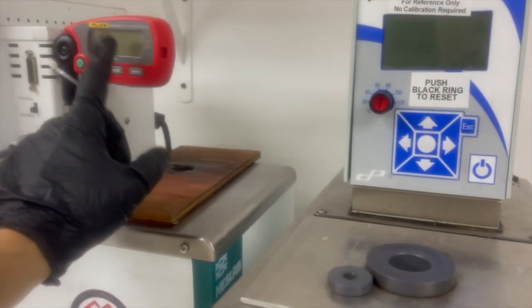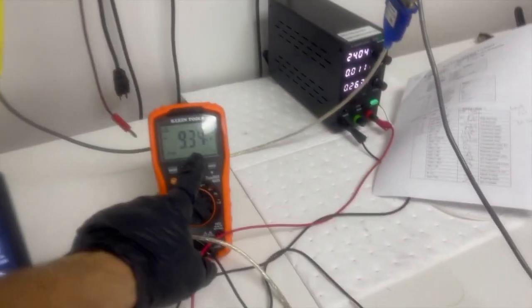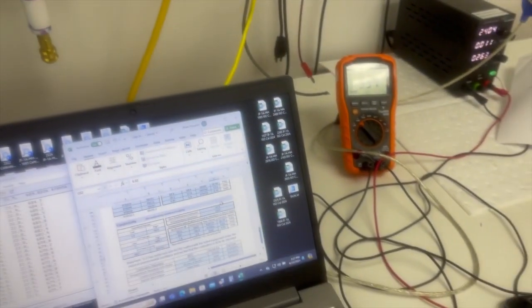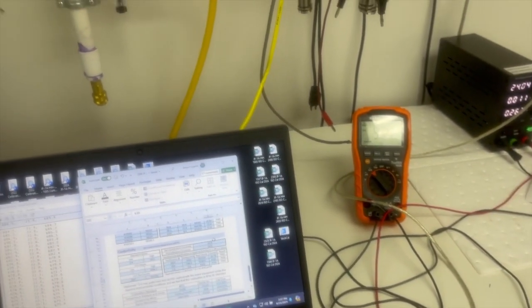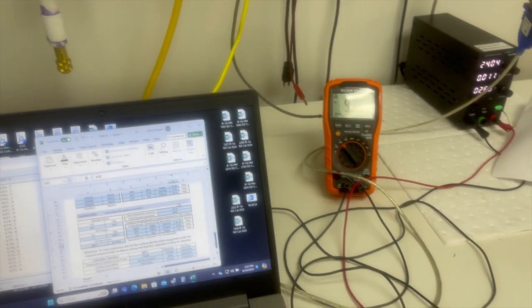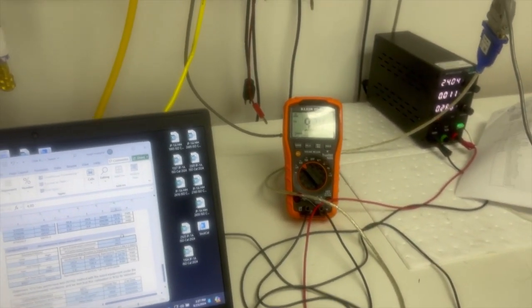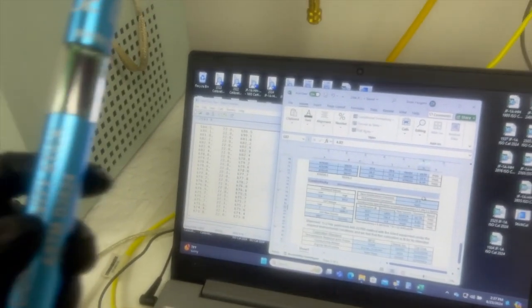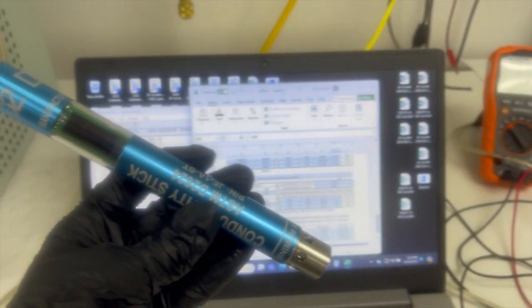You do have to annually calibrate these, and they'll come with a little calibration sticker on them letting you know that they are calibrated, and that way you have NIST traceability on those. And this, as I showed you, calibrates itself. So with that, you can calibrate these inline sensors on your own in the field.